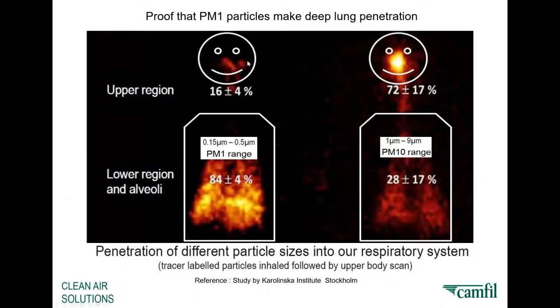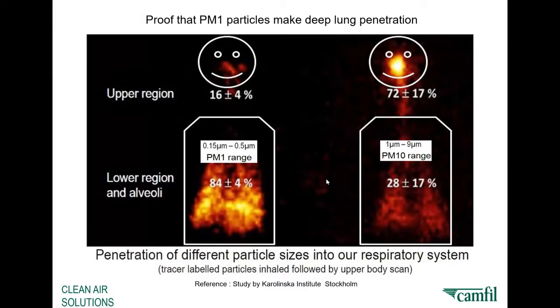And just to show that small particles are the ones that get into your lungs, this is a quick demonstration. If you look at that penetration level, 84% of particles in the 0.15 to 0.5 range, which is where typical COVID-19 aerosols and fine combustion particles from traffic usually are in the size distribution range. You can see you need protection from that by having PM1 high efficiency filters, and once you get above 1 micron, the body itself has much better removal efficiencies in the nose and sinuses, but you still do get some penetration into the deep lung. So ePM1 rated filters are very necessary for removal protection.